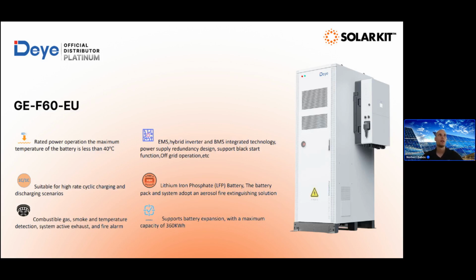From the C&I solutions of Deye, the GE-F60 is a DC coupled hybrid inverter with the battery. You have a 50 kilowatt hybrid inverter on the side and 60 kilowatt hour capacity of batteries. The batteries and the inverter are also included in the package, so it comes like this on the picture. The batteries are pre-wired inside the cabinet, so you just have to install the inverter on the side and connect the DC and the AC cables to the inverter and from the inverter to the cabinet.